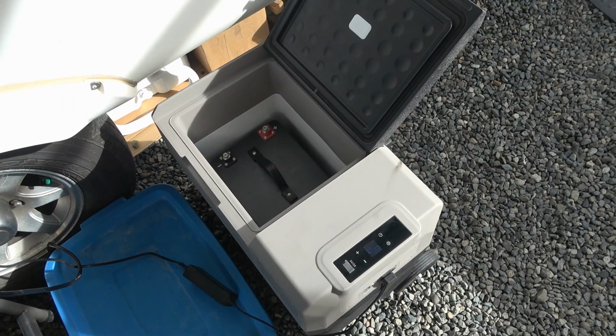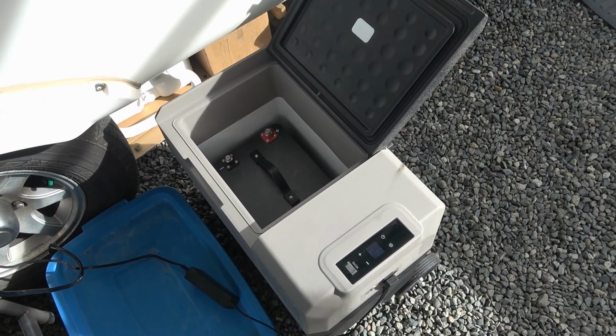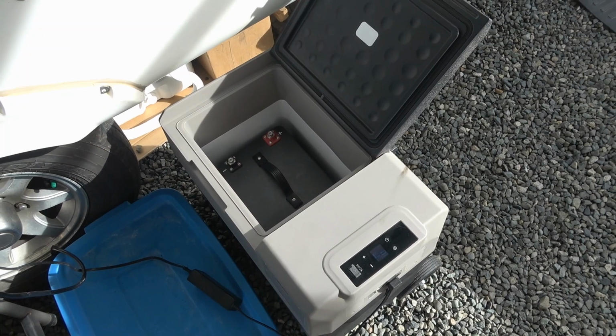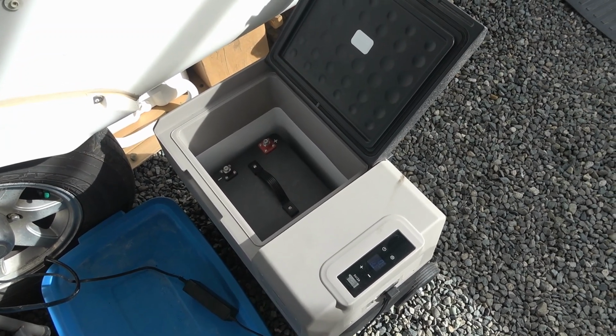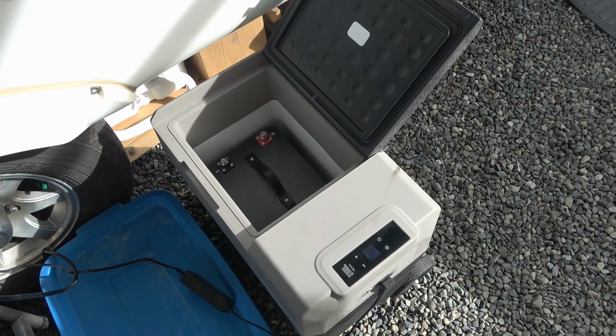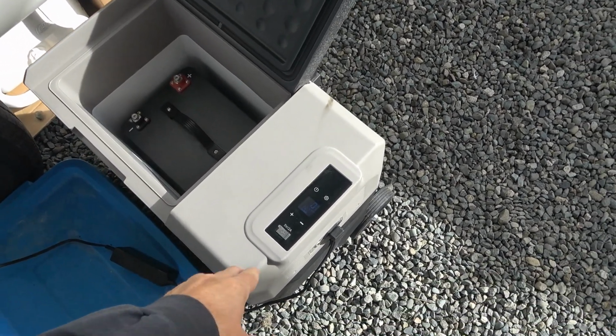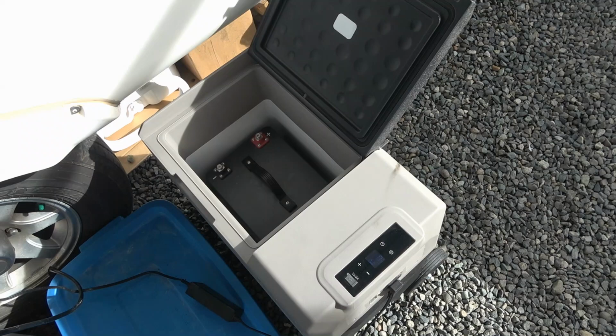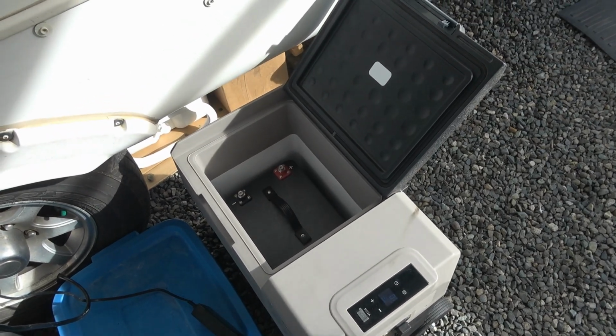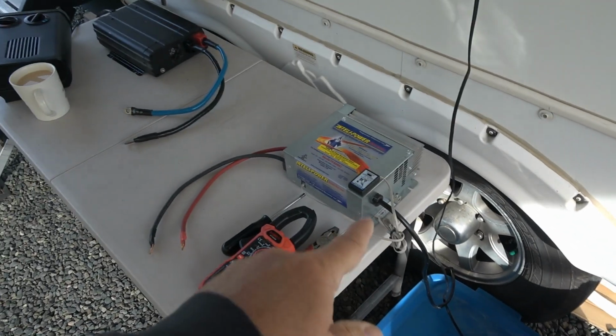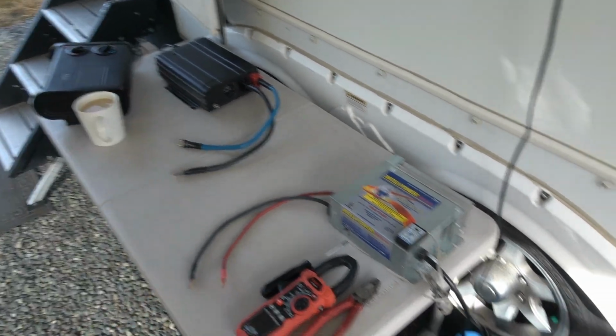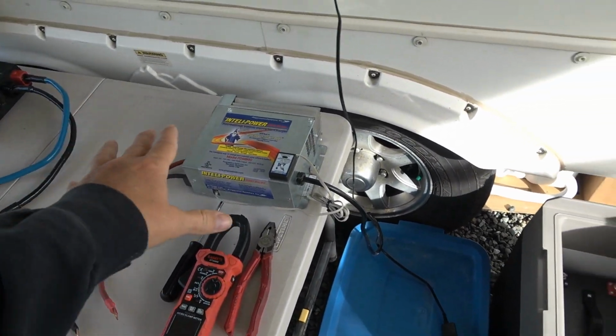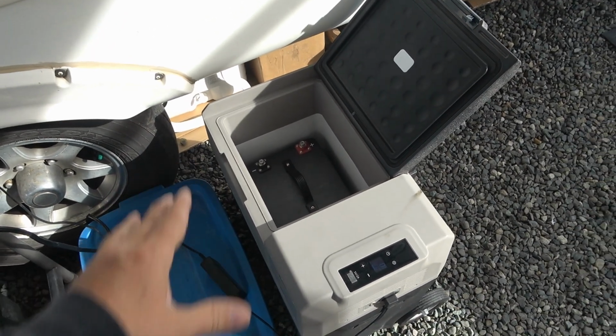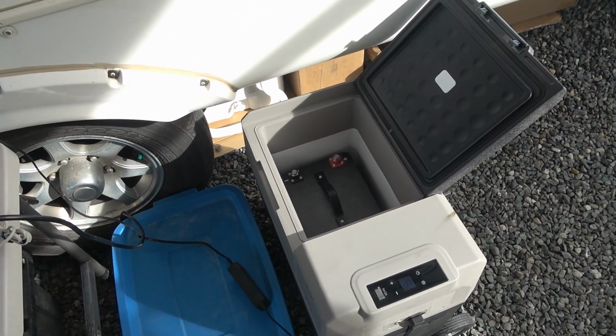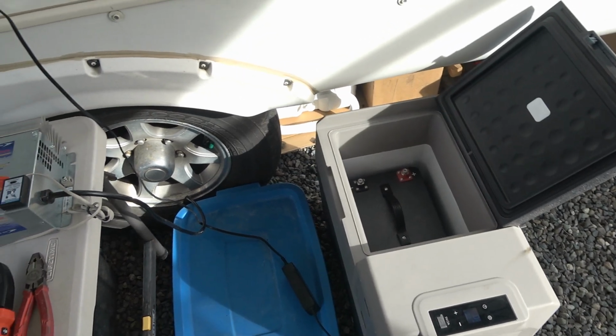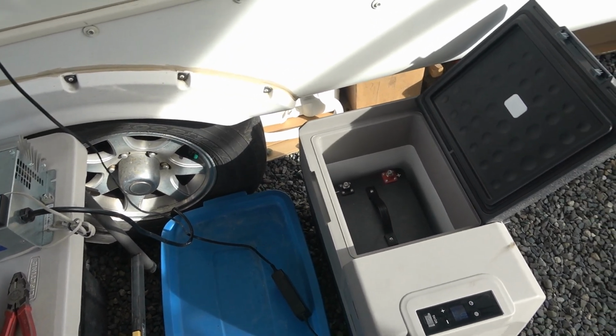Next, I'm going to test the low temperature disconnect. Now, lithium batteries don't like to be charged below about 32 Fahrenheit, 0 Celsius. So I've put the battery in my freezer here, and I'm at 0 Fahrenheit, about minus 18 Celsius. So I got a charger here and also an inverter. Now it should be able to discharge, but it shouldn't charge. I think these batteries can discharge down to about minus 4 Fahrenheit, probably about minus 20 Celsius.